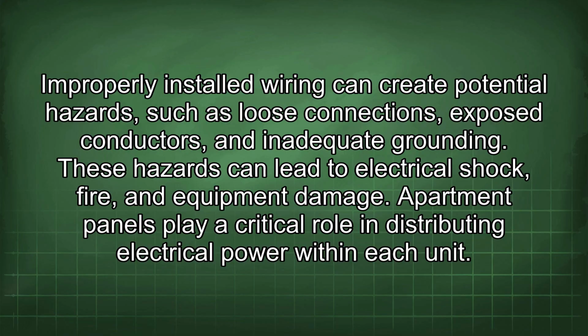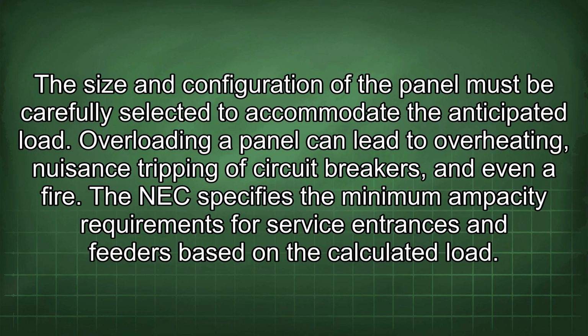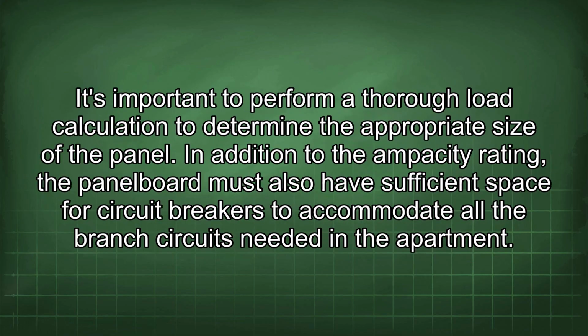Apartment panels play a critical role in distributing electrical power within each unit. The size and configuration of the panel must be carefully selected to accommodate the anticipated load. Overloading a panel can lead to overheating, nuisance tripping of circuit breakers, and even a fire. The NEC specifies the minimum ampacity requirements for service entrances and feeders based on the calculated load. It's important to perform a thorough load calculation to determine the appropriate size of the panel. In addition to the ampacity rating, the panel board must also have sufficient space for circuit breakers to accommodate all the branch circuits needed in the apartment.